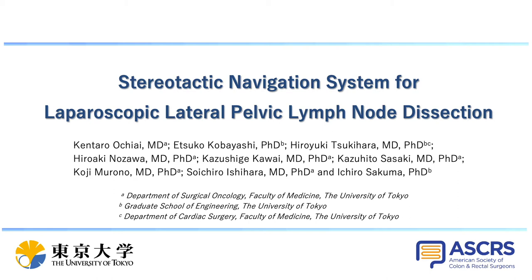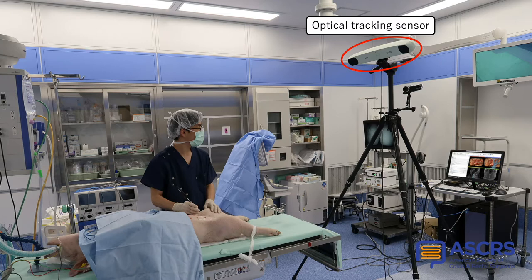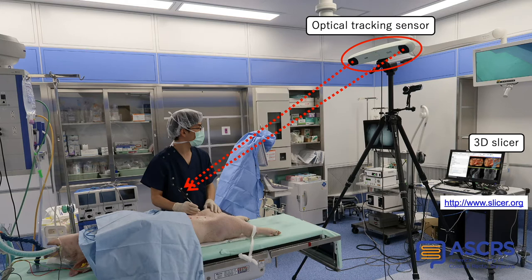Stereotactic Navigation System for Laparoscopic Lateral Pelvic Lymph Node Dissection. An overview of the system and the setup in the operating room is shown here. The system was built using NDI Polaris, an optical tracking sensor, and the open-source software 3D Slicer. The positions of the forceps and scope in the surgical field are tracked in real time during surgery using optical tracking sensors.